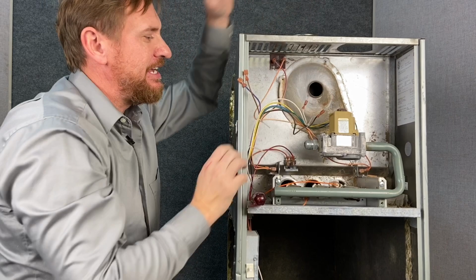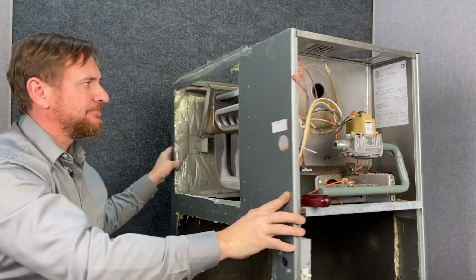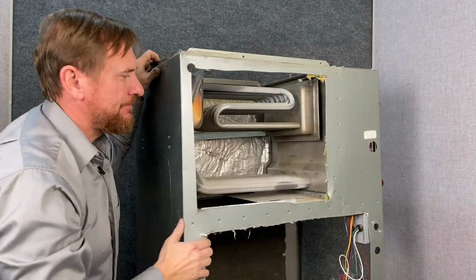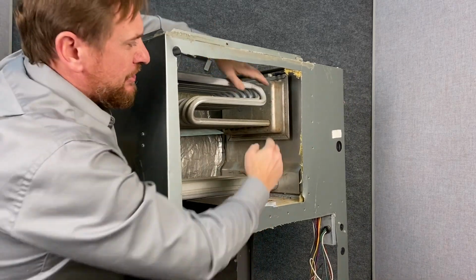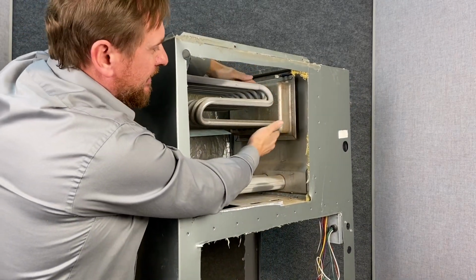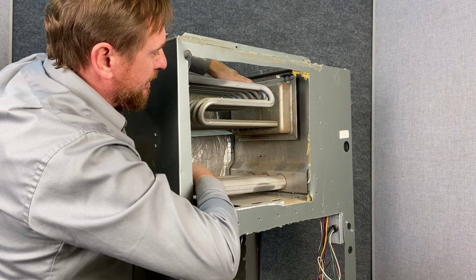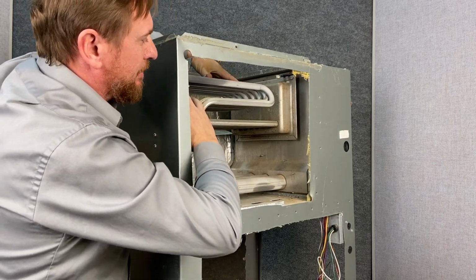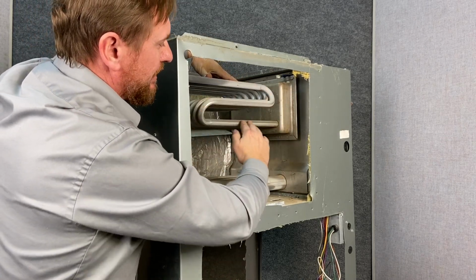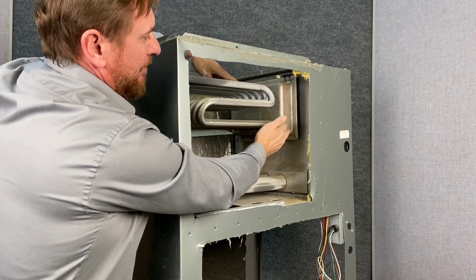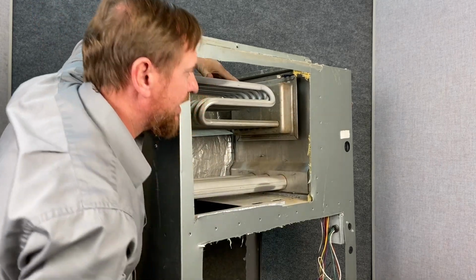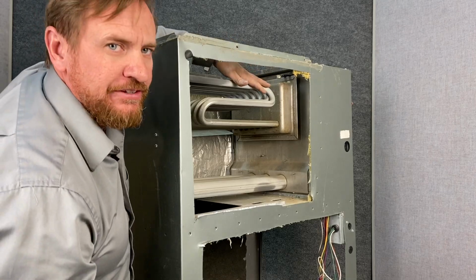Behind this, we have our heat exchanger. I'm going to turn this to the side. Heat exchanger, right in here, this is a collector box. So our main fire is going to burn here to the secondary collector box, and we go through here to make it more efficient, and all the gases gather together right here. So this inducer fan motor is pulling from all of these tubes equally.